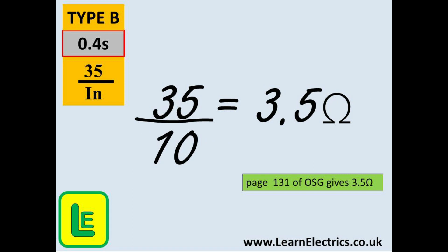Now we can try the formula for a 10 amp circuit breaker. Type B again and still a 0.4 second disconnection time. 35 divided by the 10 amp rating gives us a maximum measured ZS of 3.5 ohms. If our actual circuit measurement is less than 3.5 ohms then we have a good circuit as far as ZS is concerned. And look at the figures given on page 131 of the on-site guide for a type B 10 amp breaker: 3.5 ohms. And that is exactly the number that we have.